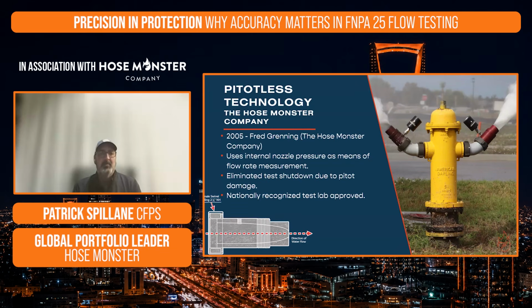And Fred Grenning, the founder of Hose Monster, determined that there's a different way to measure water flow. And that's where he came up with our pitotless nozzle technology, where we take an internal nozzle pressure reading off the side of the nozzle. And as that nozzle narrows down, it creates a nice laminar solid flow. So we get a very accurate reading. And not only do we get an accurate reading, but there's no equipment to break, get clogged, or get damaged during the test, as all the debris passes through the water flow. And then we're just taking a pressure reading at the side port of the nozzle.